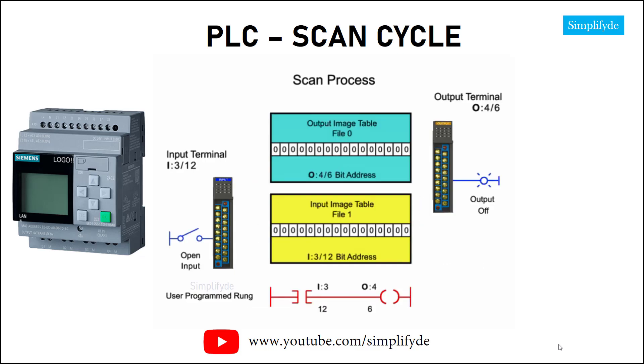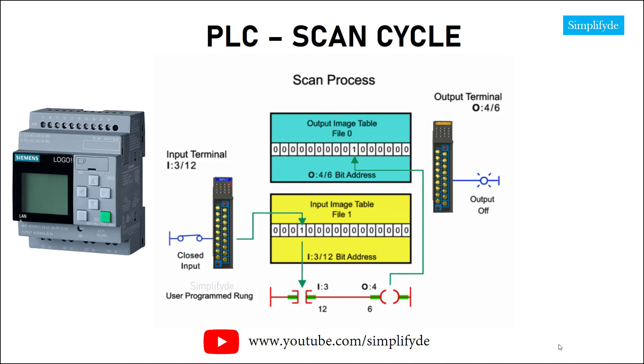The entire scan process is demonstrated further here. When the limit switch is activated, the input module detects a voltage and an ON condition is updated in the input table with a value of 1. During the execute program step, the PLC sets the input and output instructions ON.